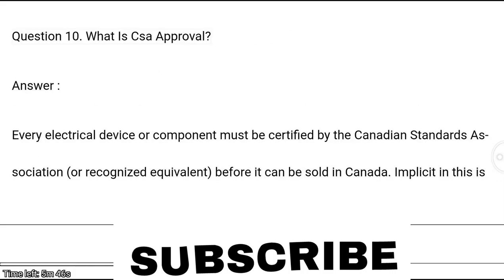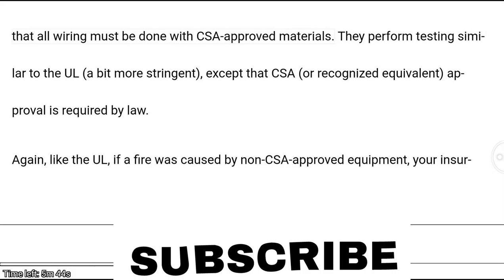Question 10: What is CSA approval? Answer: Every electrical device or component must be certified by the Canadian Standards Association or a recognized equivalent before it can be sold in Canada. Implicitly, all wiring must be done with CSA-approved materials. They perform testing similar to UL but more stringent, and CSA or recognized equivalent approval is required by law. If a fire was caused by non-CSA-approved equipment, your insurance company may not have to pay the claim.